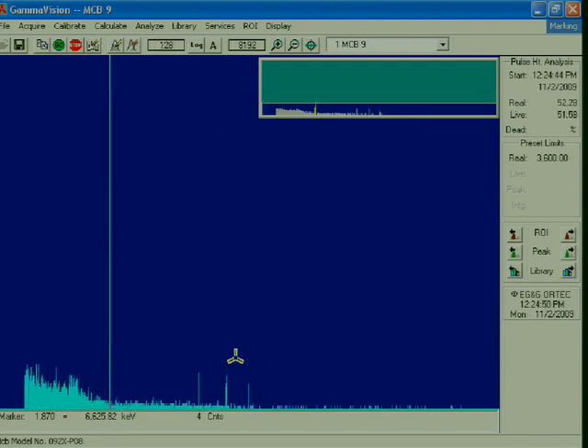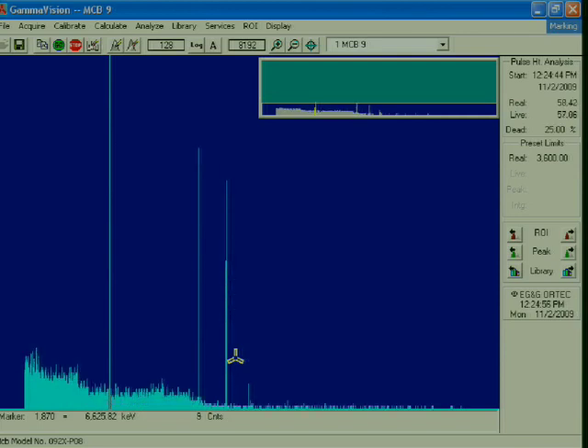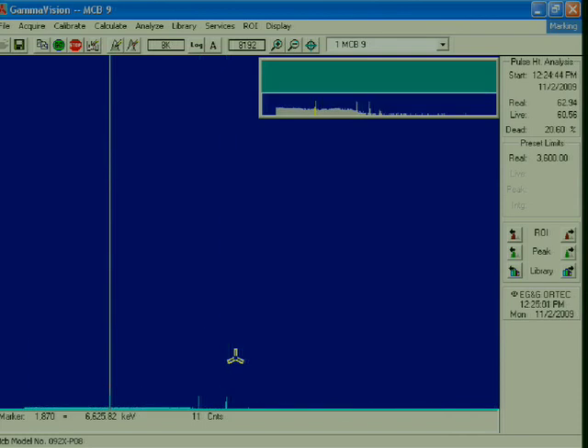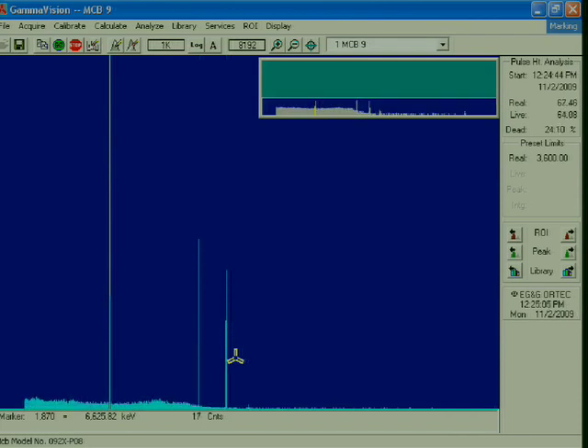And it's a little weaker. Let's bring it over here. Okay. Now it's counting pretty fast. So remember, the cobalt-60 has 2 gamma rays, 1173 keV and 1332, and the cesium has 1 gamma ray at 662 keV. And we can use them then to allow the electronics to convert channel numbers into real energies.